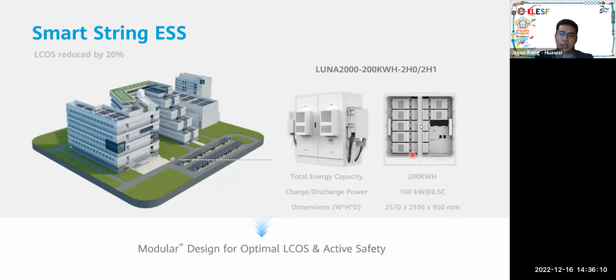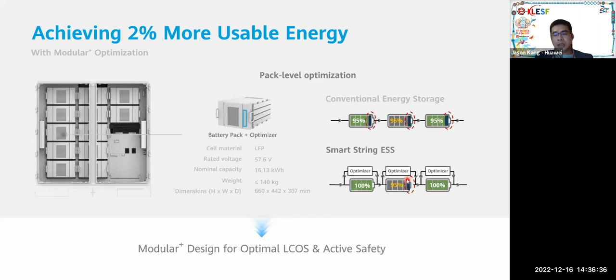If you have a faulty pack, it will be auto isolated. If you want to replace it with a new battery pack, it's a plug and play configuration, so there's no need for SOC adjustment. In regards to safety, we also have multi-level shutdown protection and rapid system disconnection to isolate any fault in the packs.